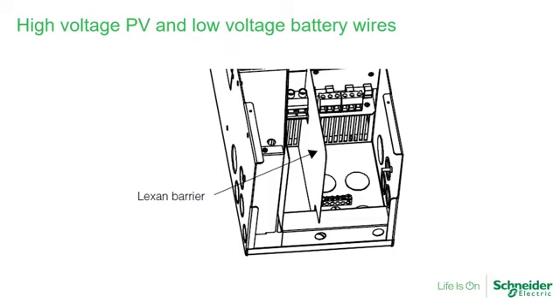So this side is the array, which could be up to 600 volts, and this other side is to the batteries, and that's 48 volts. So you don't want to mix those two. The barrier is actually part of the UL listing of the product, and you don't want to mix the two wires.